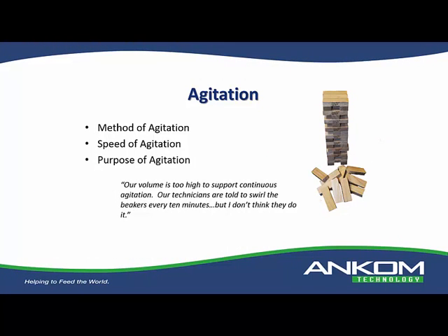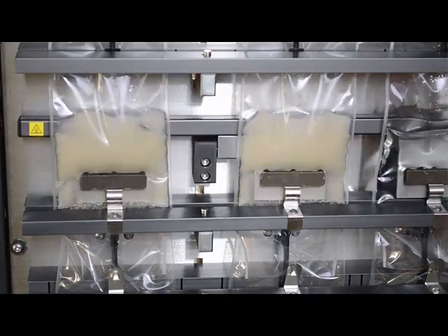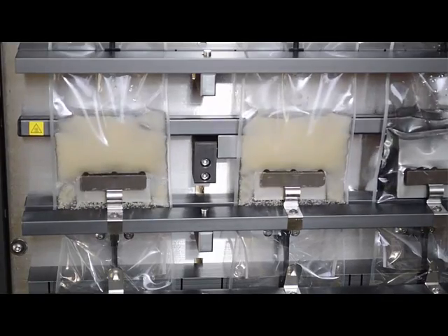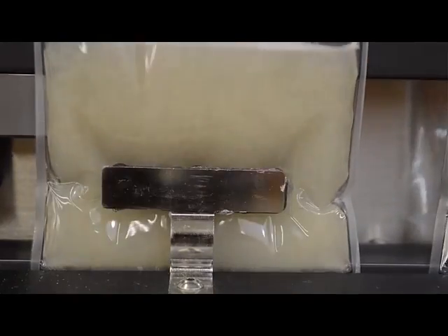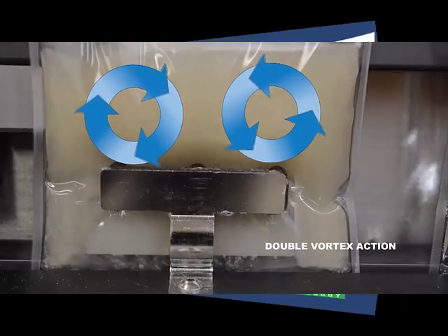Agitation is an important element because during the enzyme digestions you want the sample to have a lot of surface area — suspended throughout the liquid — in order for the enzymes to do their job. The methods have different callouts for the type of agitation. Some are very specific and state revolutions per minute; some just say continuous or periodic agitation. As different labs do different things, it could be a problem. I had one customer that said agitation alone justified the automated system because currently they could not agitate samples and told technicians to every 10 minutes swirl the beakers out of the water bath. If the sample is not fully suspended, it's going to impact the results.